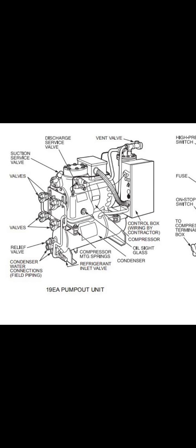So the storage tank has low pressure and the pressure is high in the chiller. It will push, just pushing the liquid. So all the liquid is pushed and comes into the storage tank. Same like this pump down. After you think all the liquid refrigerant is out from the chiller, you have to change the cycle.